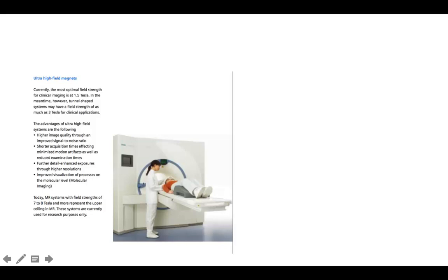However, as you go to 3 Tesla, you have some clear advantages. You get better image quality because your signal to noise ratio is considerably improved. You have shorter acquisition times because your field strength is higher and your signal to noise ratio is better. And you have reduced motion artifacts. And it's more comfortable for the patient because a 1 hour scan becomes a 20-minute scan or a 30-minute scan.